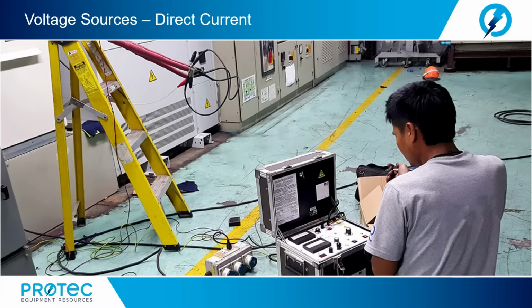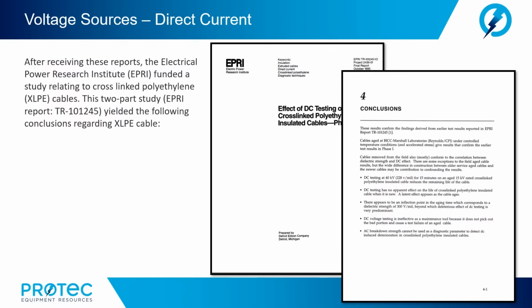However, as time moved on, plastic insulated cables became more abundant and began showing effects of service age. Direct current continued to be the dominant test, but concerns began to grow over the effectiveness of this test. In the early 1990s, reports started to surface indicating that DC high potential testing could be to blame for latent damage experienced by extruded medium voltage cable insulation, particularly cross-linked polyethylene and ethylene propylene rubber.